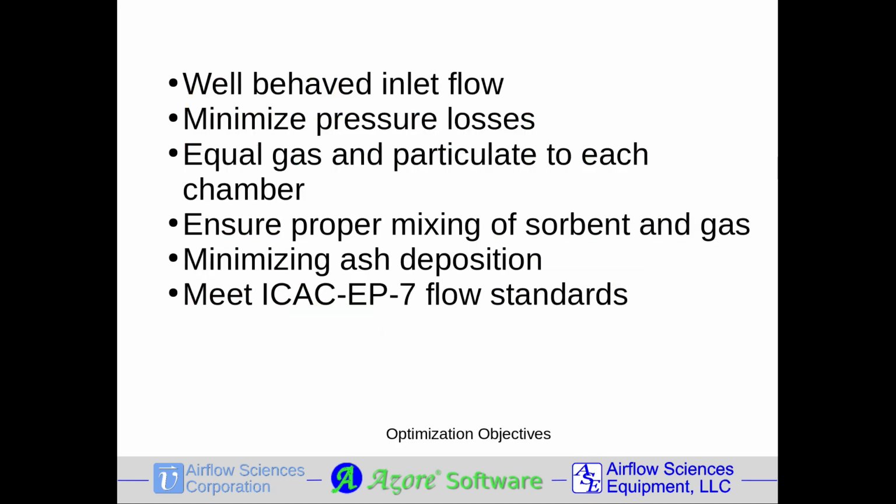Combining the Institute of Clean Air Companies (ICAC) standards with manufacturing and final customer requirements, specific objectives of an ESP study will usually include ensuring that gas flow entering the inlet nozzle and each chamber is well behaved, minimizing pressure losses throughout the system, ensuring an equal flow split of gas and particulate to each chamber, ensuring proper mixing and interaction between any sorbent and gas, and minimizing ash deposition.